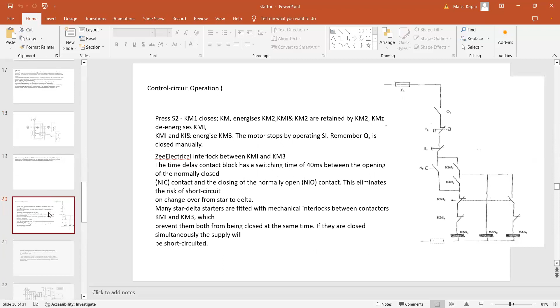Yesterday we finished with the star delta, right? Yes sir, and some time delay and all is remaining. So this is how the time delay is connected. This KM2 relay is only acting as a time delay. KM2 has a pair of... sir, which time delay are you talking about sir? Timer switch? There should be some time delay between star and delta, both shouldn't switch at the same time, right? Yes, otherwise it will short circuit.